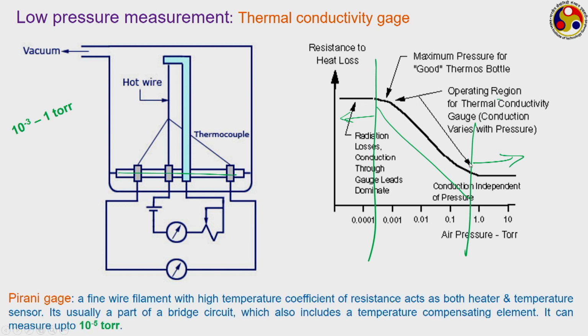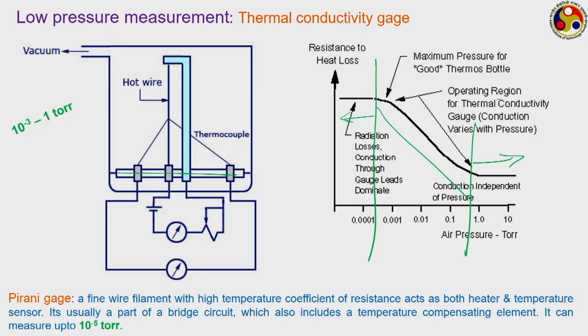Another variation of this thermal conductivity gauge or thermocouple gauge is called the Pirani gauge, where instead of a separate heater we are using just the same filament, which acts as both the heater and the sensing element. Here this filament is generally part of a Wheatstone bridge kind of circuit, just one of the 4 arms. We may also have a temperature compensating device to limit the temperature within a range. And this Pirani gauge, despite being just a variation of the thermal conductivity gauge, can give you even lower pressure, can go up to 10 to the power minus 5 torr levels.